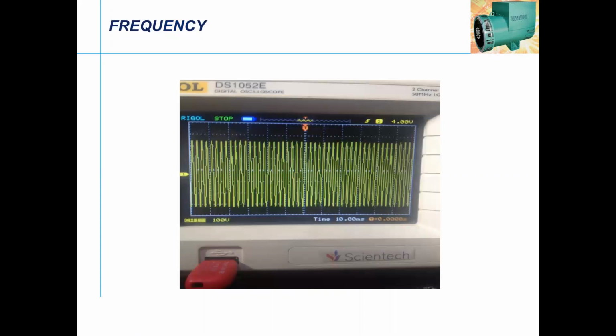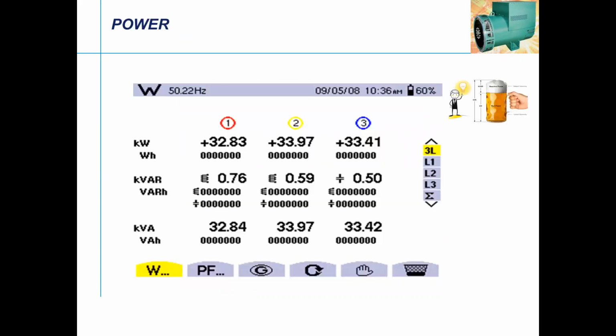This AVR also monitors the frequency, what it is going to put across. And this we can see in our own digital AVR. Previously this was monitored from a different machine, different monitoring equipment. Today, you can monitor the voltage frequency in this AVR. That is the advantage. And all put together, it comes to your kilowatt, kVA, and kVAR. This is what is fundamental in a generator.